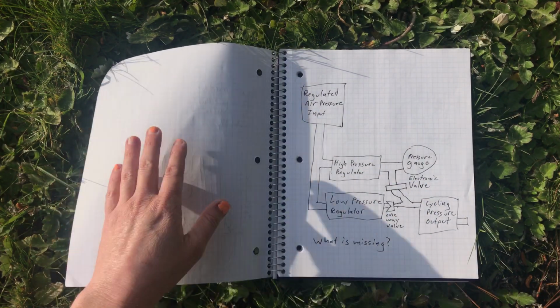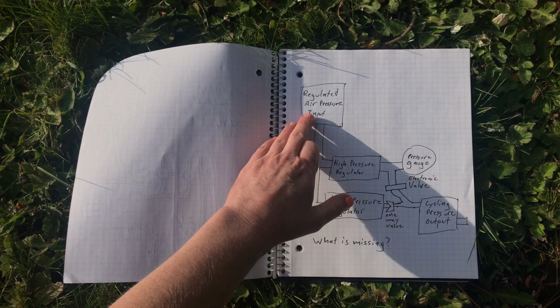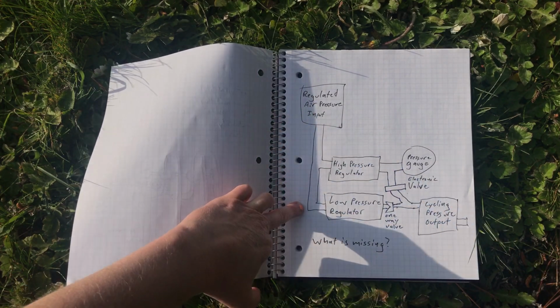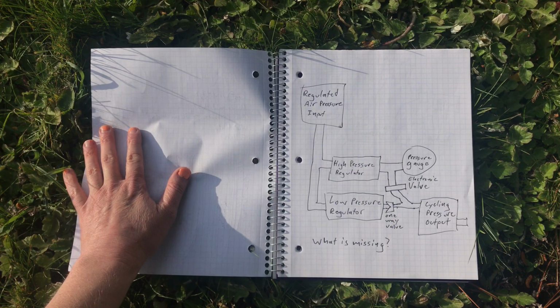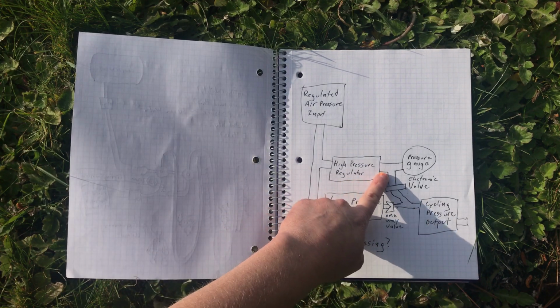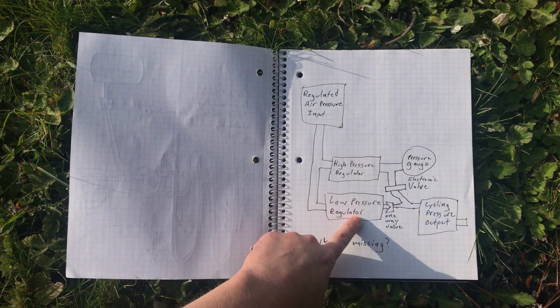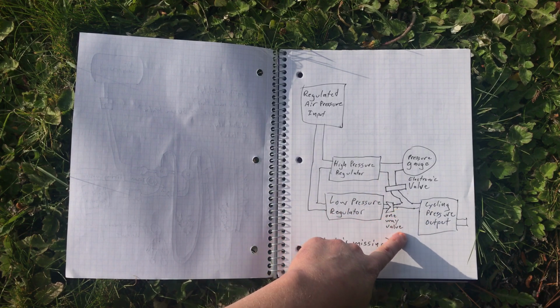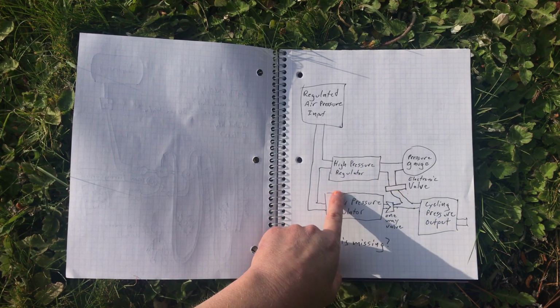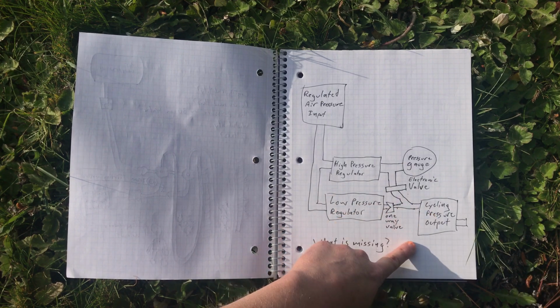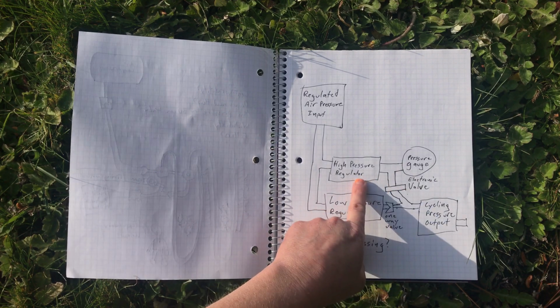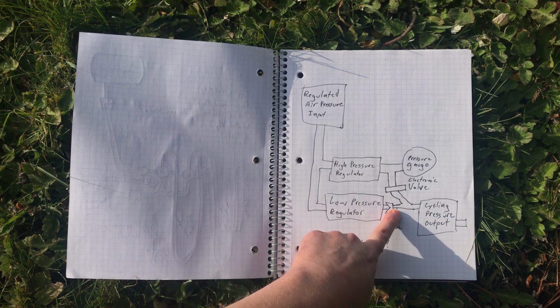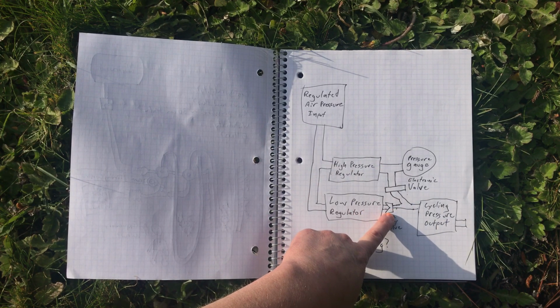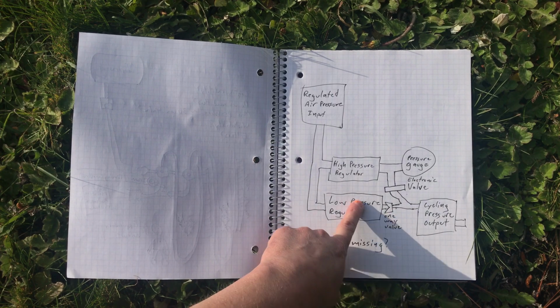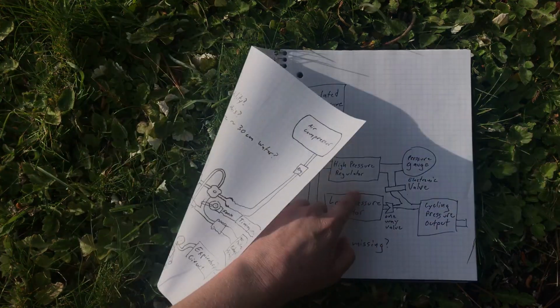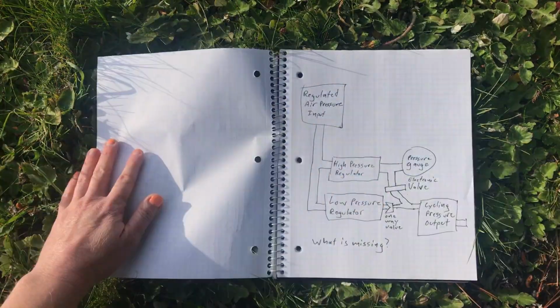I'll show a little more diagram on the next page, but first let me just discuss this. So you have high pressure or line pressure coming in here, and then this pressure regulator is designed for the patient's desired maximum pressure, and then the patient's desired low pressure here. When the electronic valve is closed, only low pressure feeds to the patient. When the electronic valve is open, then high pressure feeds into the patient, and it does not backflow here because there's a one-way valve. In fact, you don't strictly need this one-way valve because if you have highest pressure here, then this would not backflow with this regulated output.